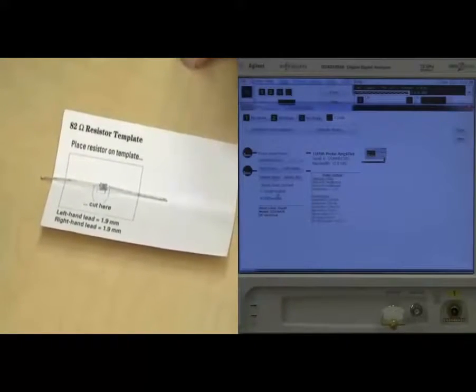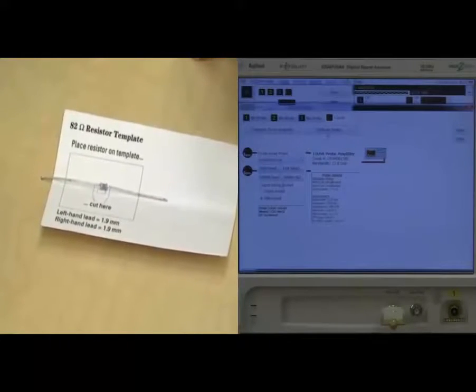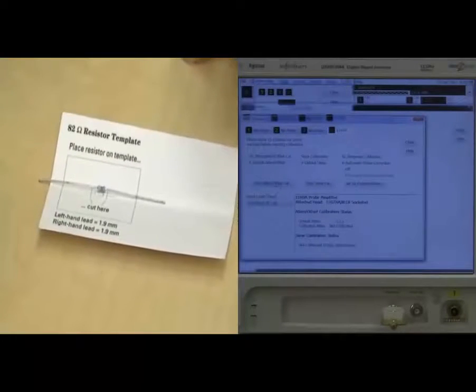Single-ended or differential does not matter for the purposes of calibration. We want to select that later when it's time to actually use the probe. So then we can select calibrate probe, and we want to select start attenuation and offset calibration.